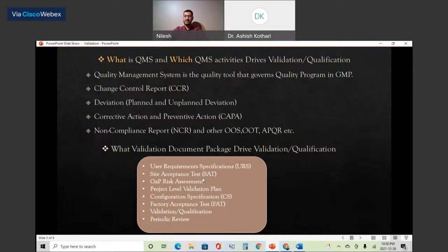In risk assessment, you will decide how often you need to revalidate the process or equipment. It may be annual revalidation, biannual, or every 5 years. If you have a high risk to the product or to the equipment, you need to revalidate the same equipment every year. And regulatory bodies always want to see how you designed your risk assessment and how often you are revalidating your system.